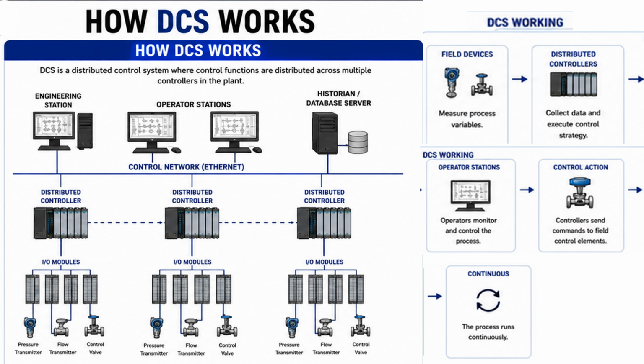Engineering stations. Now look at the top of the DCS diagram. You can see several computers. Each one has a different job. The engineering station is where engineers create and modify the control logic. The operator station allows operators to monitor the entire process in real time. They can see temperatures, pressures, flows, motor status, alarms, and trends, all from one screen. The historian server records process data continuously. This information can later be analyzed to improve efficiency, reduce energy consumption, or troubleshoot problems.